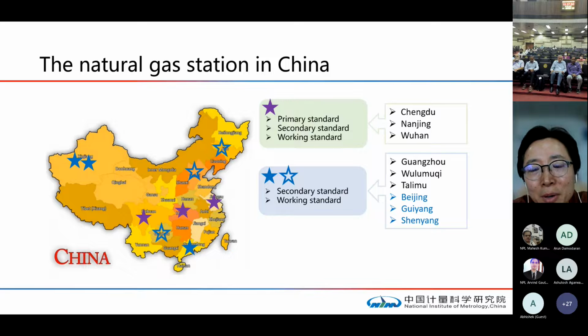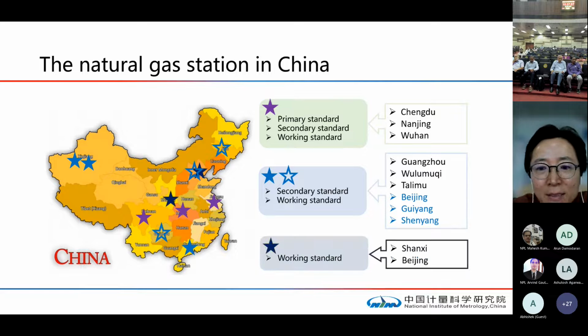They don't have the primary standard, they only have the working secondary standard and working standard. And in recent years, we also build 2 additional natural gas stations in Shanxi and Beijing. They don't have the primary and secondary standard. They only have the working standard to achieve the calibration of the flow meters.